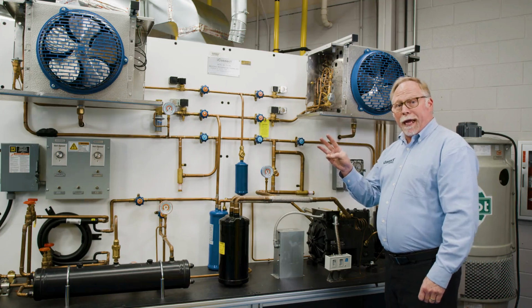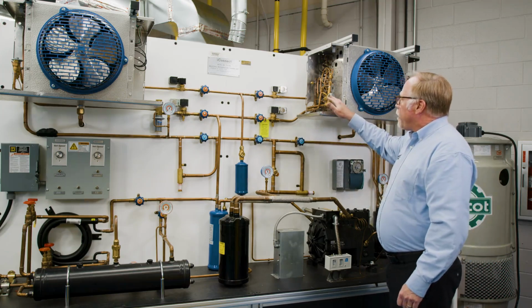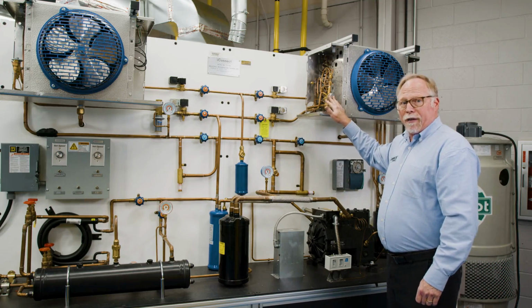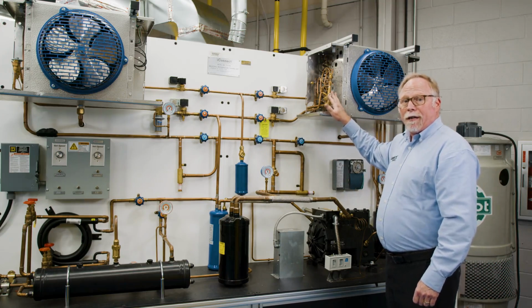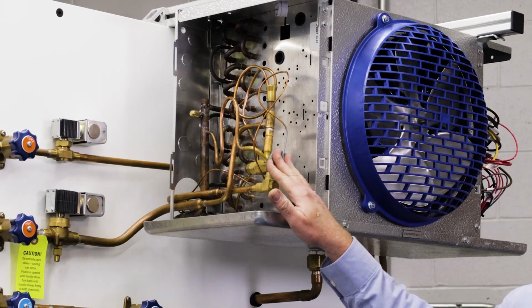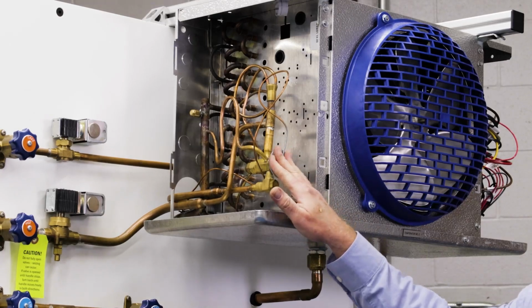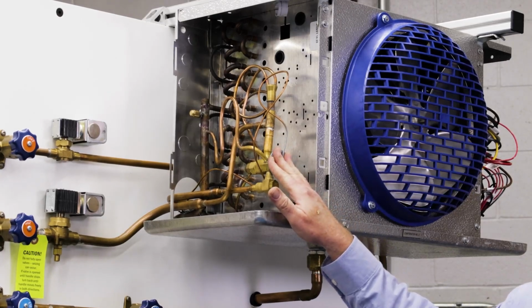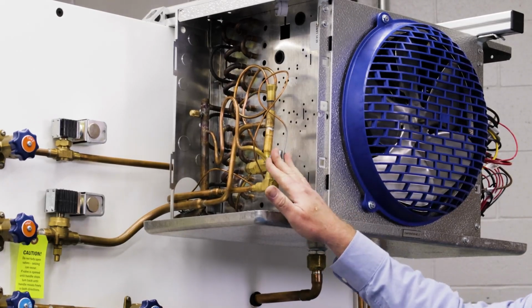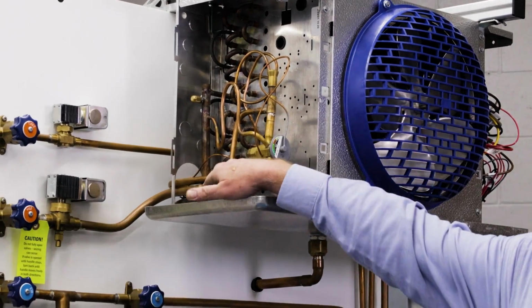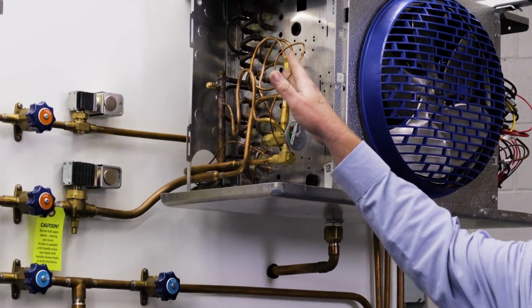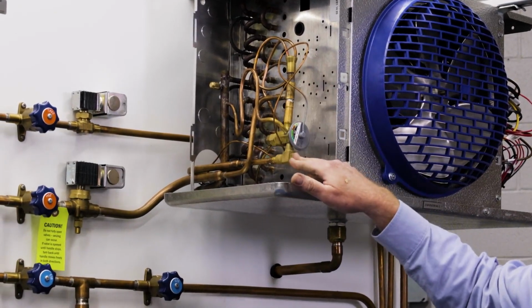Lesson number three would be to explain the thermostatic expansion valve. Here you have an opportunity to talk about the different types of thermostatic expansion valves, external bypass versus non-external bypass, and the reason you would have one. Also, you can use this to teach how to measure subcooling, how to troubleshoot superheat, and how to adjust the expansion valve.